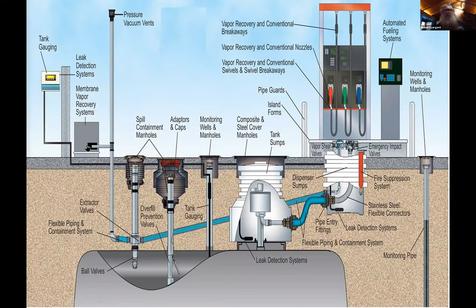Here's all the equipment involved with your UST system — there's a lot to be aware of. Monitoring wells — you don't usually have those on new systems now; they're more of an external leak detection method, though they're still useful for telling if you've had a release. Ball float valves are something you can't use on new installations — they've been phased out for the most part. Vacuum lines and membrane vapor recovery systems are only on stage two vapor recovery systems, which are basically only in California and possibly Washington DC anymore.